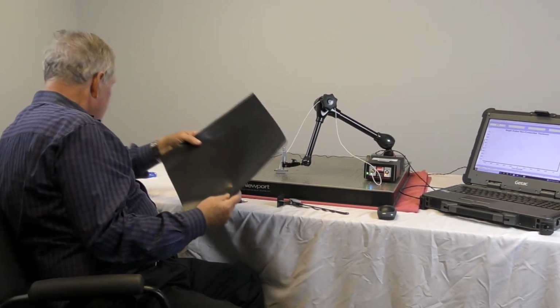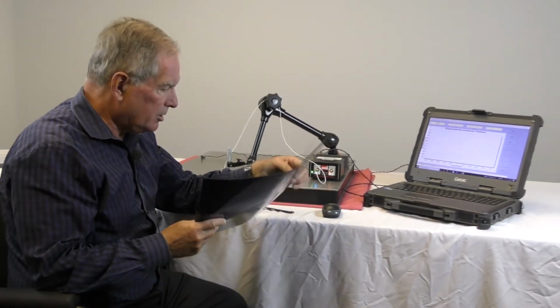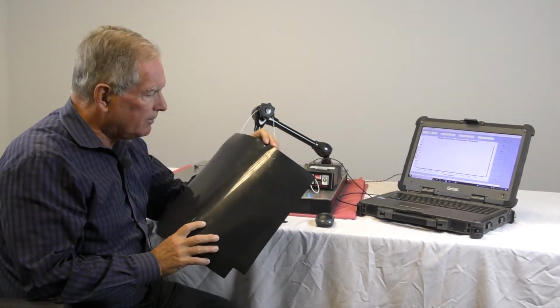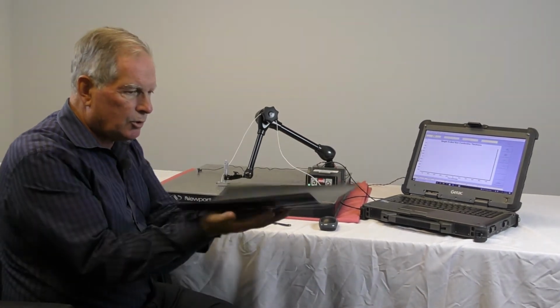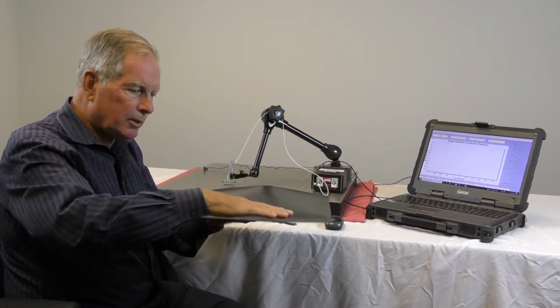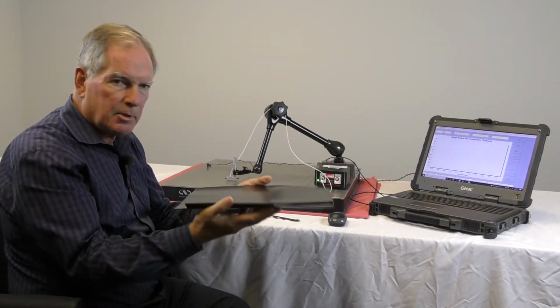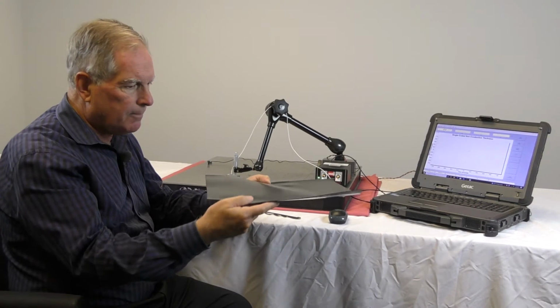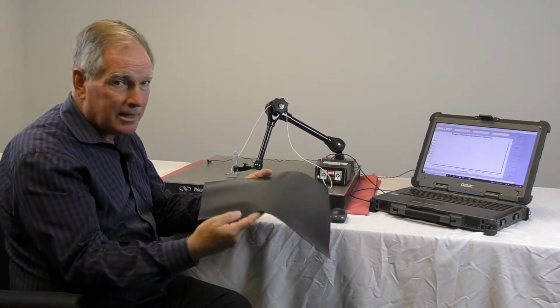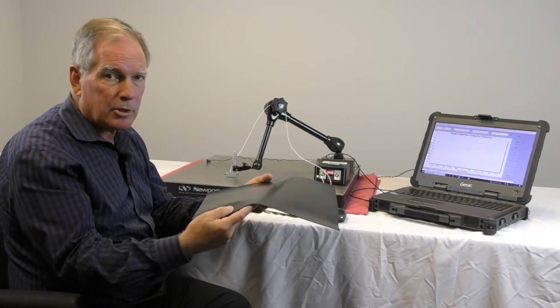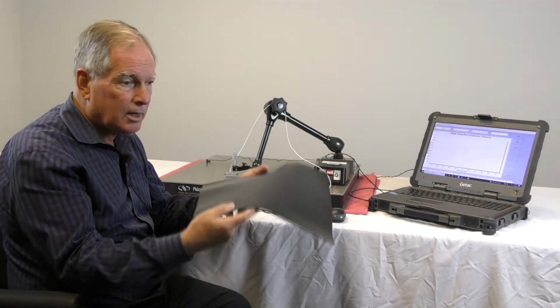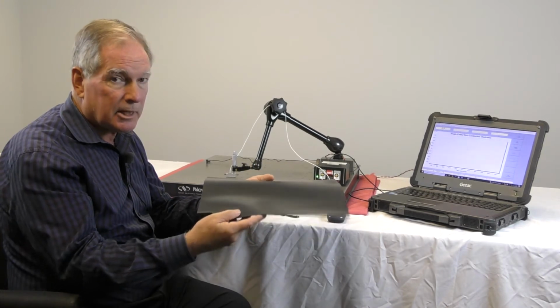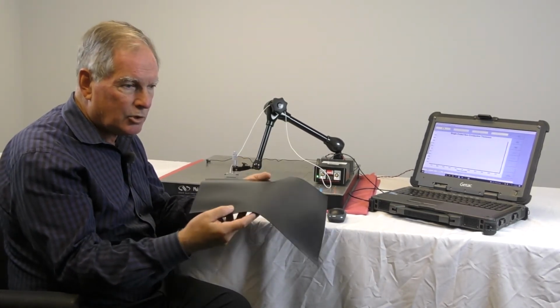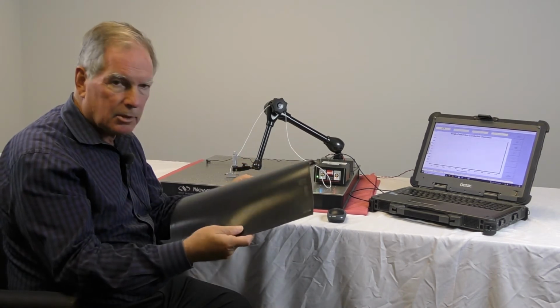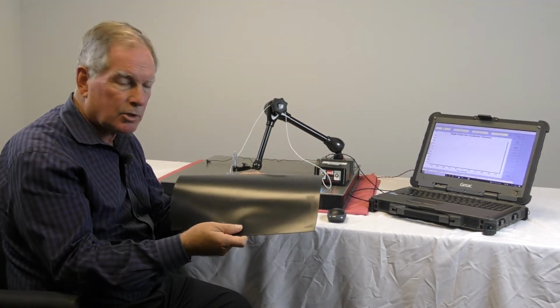The other thing is that we don't want paper backing on these things either. This does have a backing on it. It's probably a polyethylene backing, which acts as a substrate when they make this stuff to hold the material. As they're pouring the goop on here before it dries, that keeps it from falling down into the web. So no paper backing. Why? Because paper is pretty porous and it can absorb humidity out of the atmosphere, and we talked about water having a high dielectric constant, almost being a conductor. So paper backings absorb moisture and therefore are not good insulative materials to make measurements on.